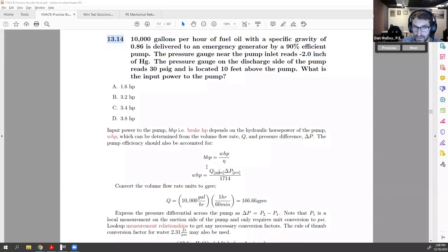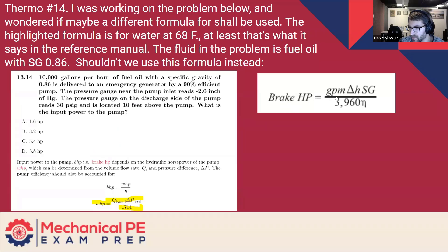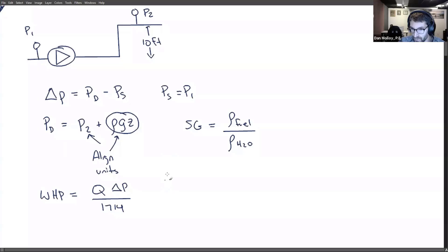If on the other hand, you want to use the other formula, which you're certainly is not wrong, then you have to account for the specific gravity. So that other formula, and I think the other formula that he showed went straight to BHP. So this is also valid. The only difference between BHP and WHP is that the efficiency is included. So I could just as, it'd be just as correct to say WHP equals GPM delta H SG over 3960 and exclude the efficiency.